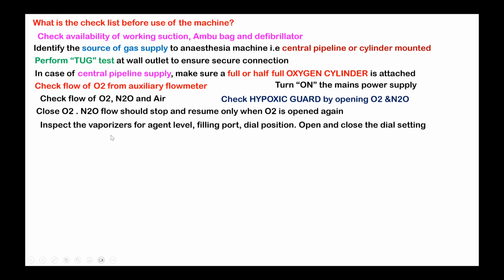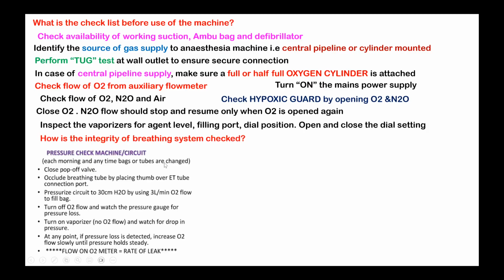Inspect the vaporizers for agent level, filling port, and dial position, opening and closing the dial setting. And then how do you test the integrity of the breathing system check? That is, close the pop-off valve, occlude the breathing tube by placing a thumb over the ET tube connection port, and pressurize the circuit to 30 centimeters of water by using 3 liters of oxygen flow.